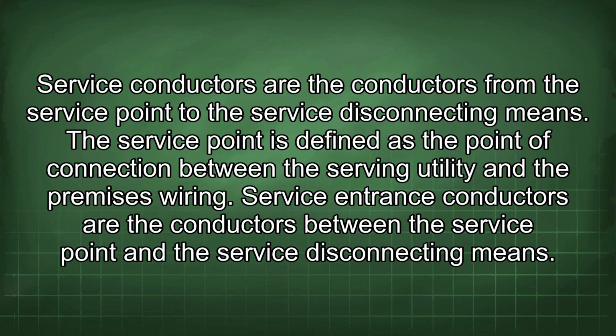Service conductors are the conductors from the service point to the service disconnecting means. The service point is defined as the point of connection between the serving utility and the premises wiring. Service entrance conductors are the conductors between the service point and the service disconnecting means.